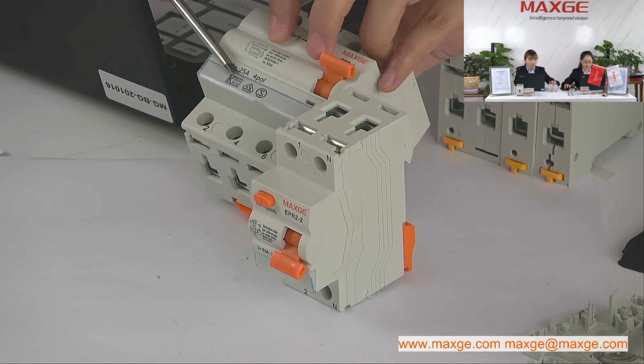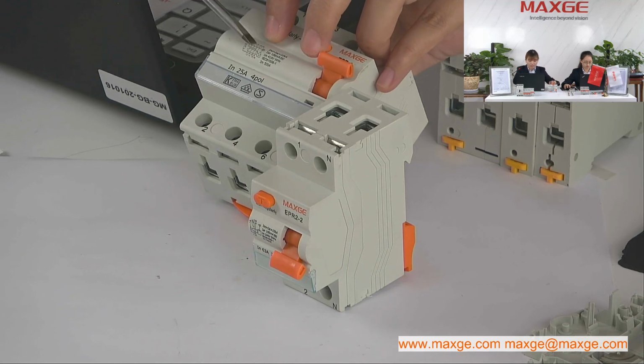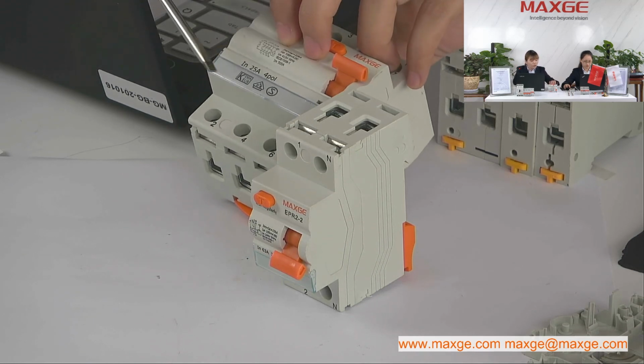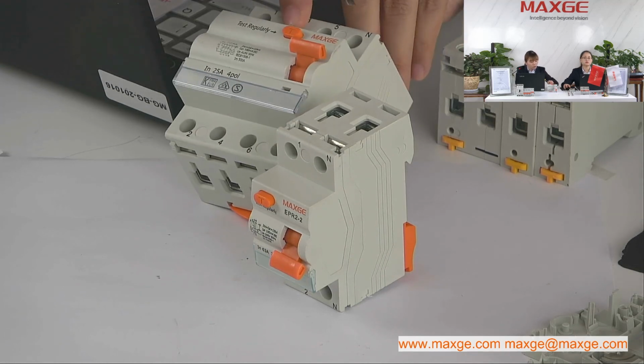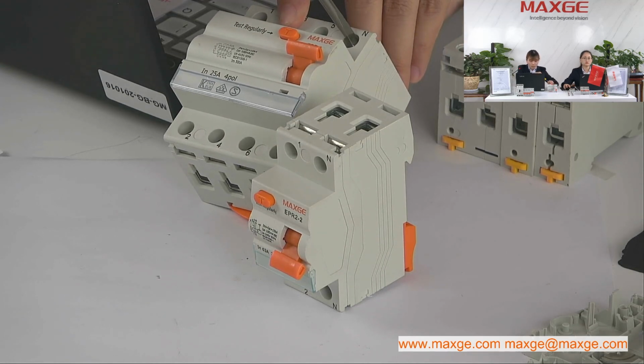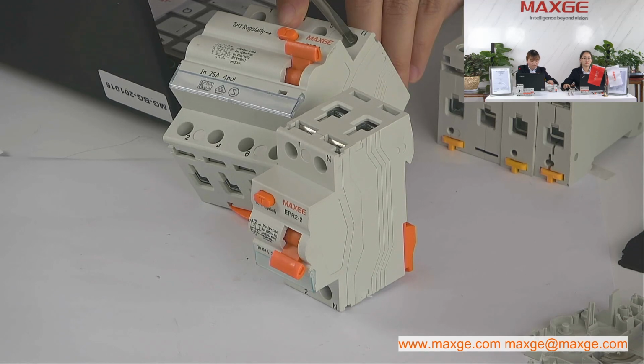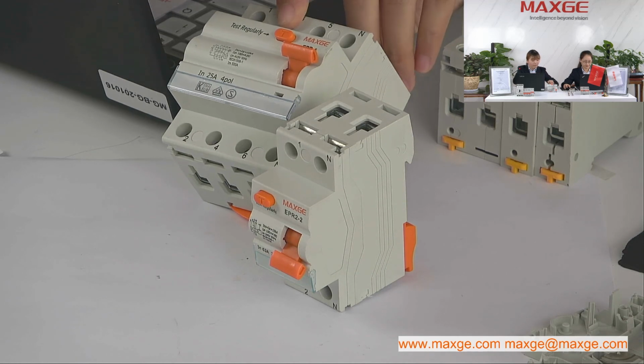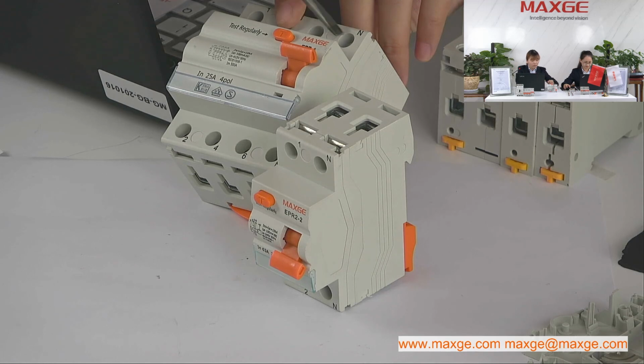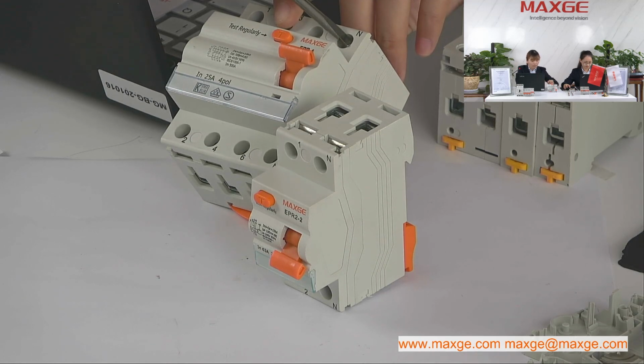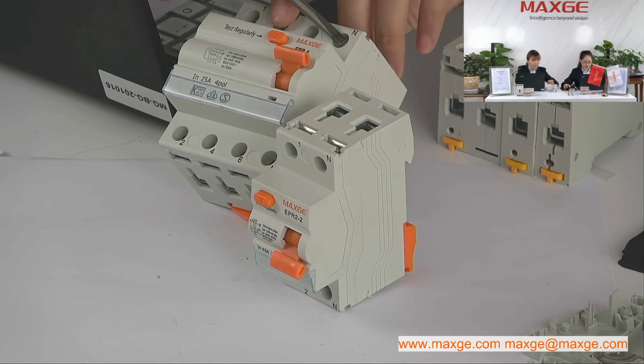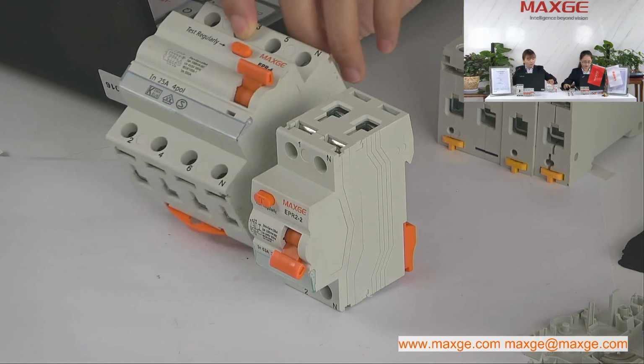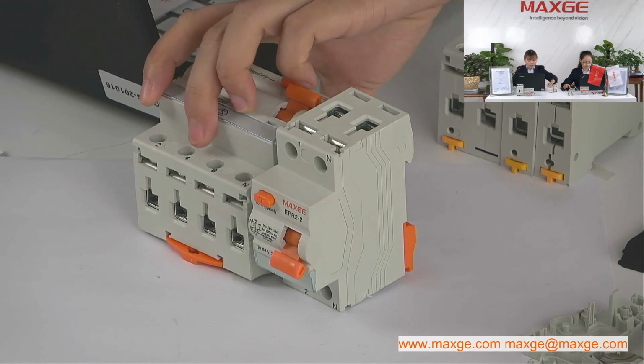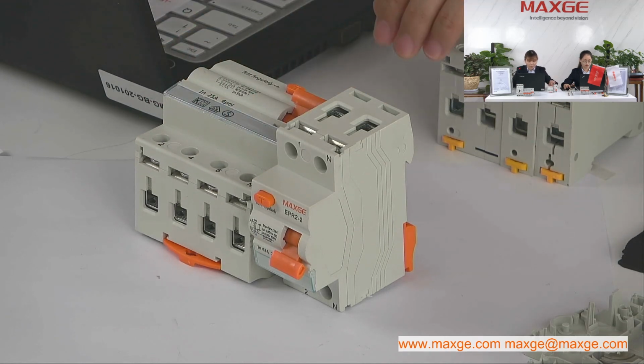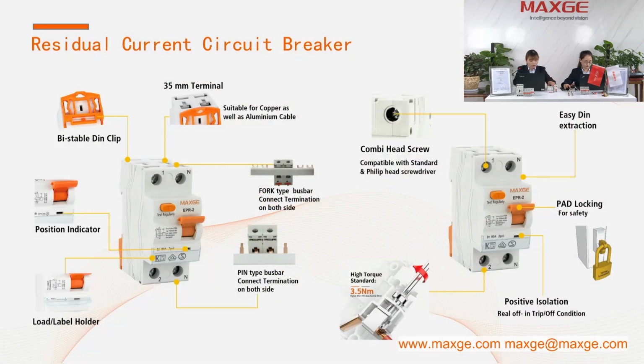And we have an advanced neutral pole. This is the neutral pole, and it closes first and opens last. The neutral pole on the left or on the right is available. You can choose according to our customers' market requirement. Now Rere will introduce our RCCB advantages.